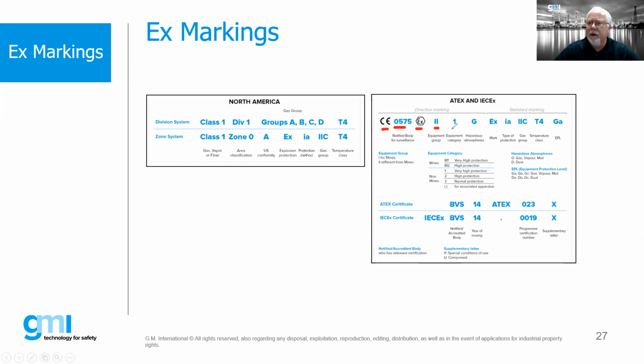Remember, we talked about equipment group 2, that's for surface areas. Then we have our category 1G, which is telling us it's suitable for a zone 0 environment. Then we get into our marking strings over here. So we have our EX IA, which is intrinsic safety, double fault tolerant. It's good for all gas groups. It has a T4. And then finally, we find our IEC-EX EPL's GA.